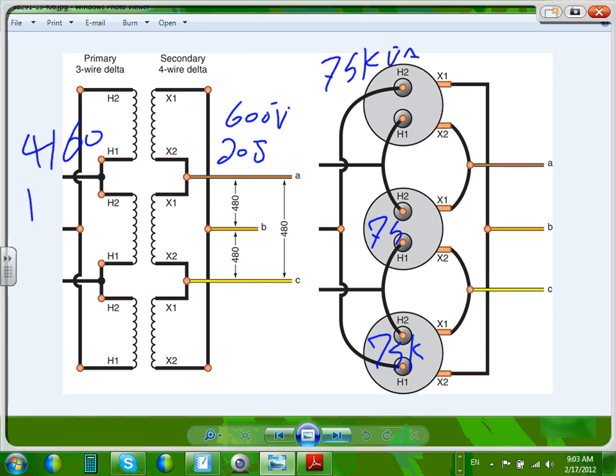This could be 13.8 kV, 12.47 kV. That's what I commonly want to emphasize, at least that's my experience with them, is we use them with high voltage on the primary. The primary is usually high voltage. I've never seen them where the primary is less than 600 volt. Usually it's higher than 600 volt.